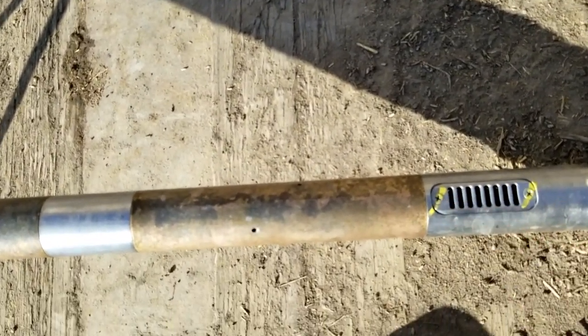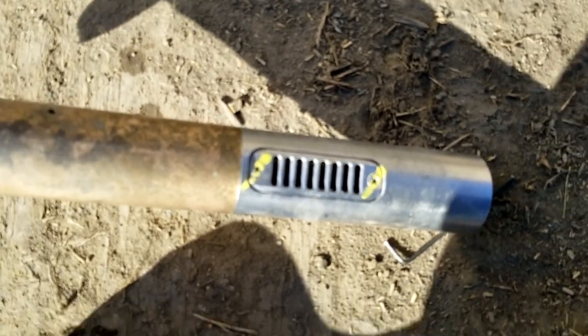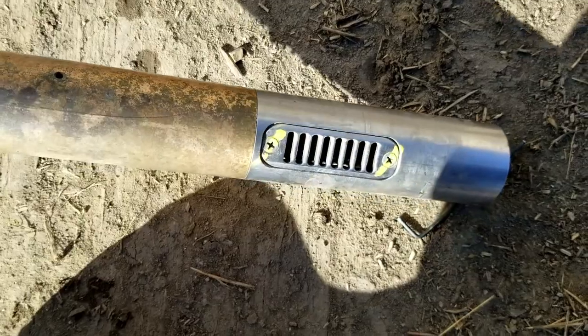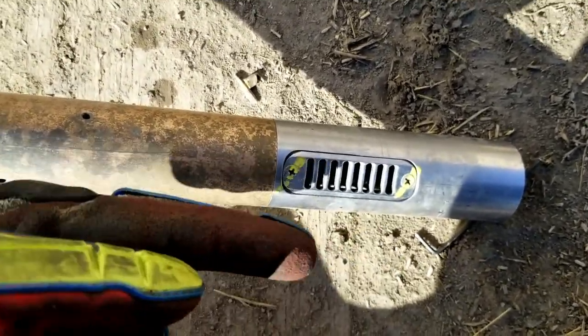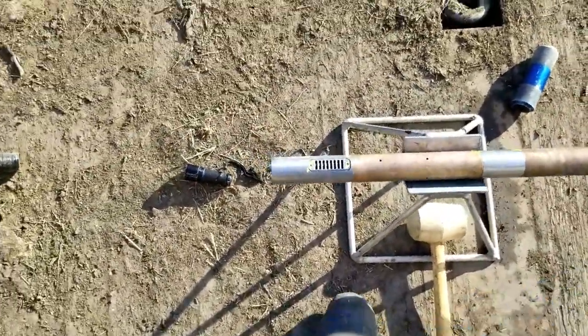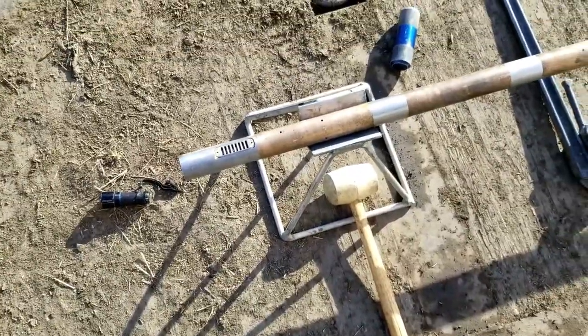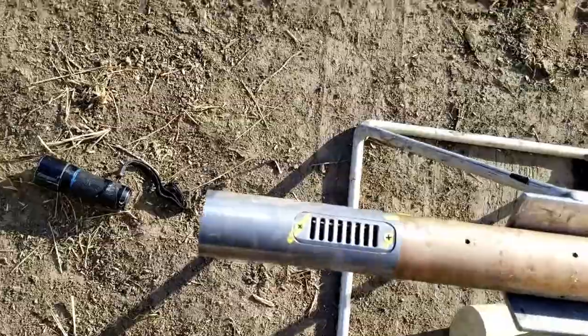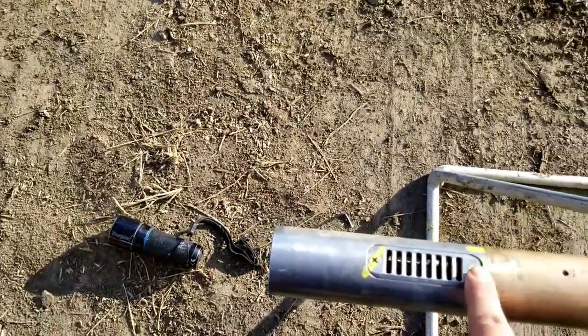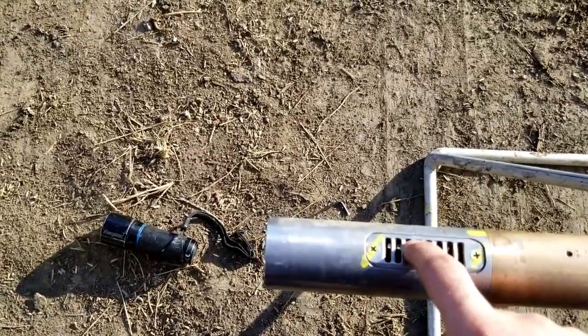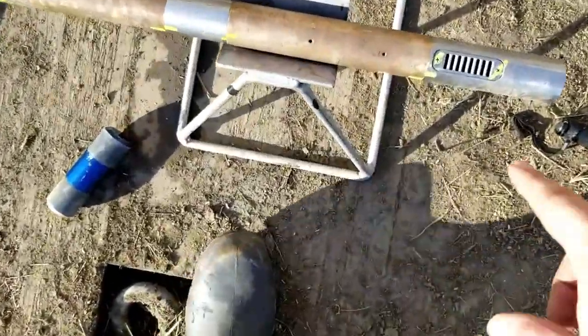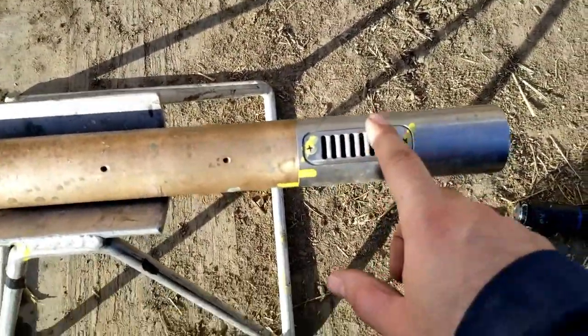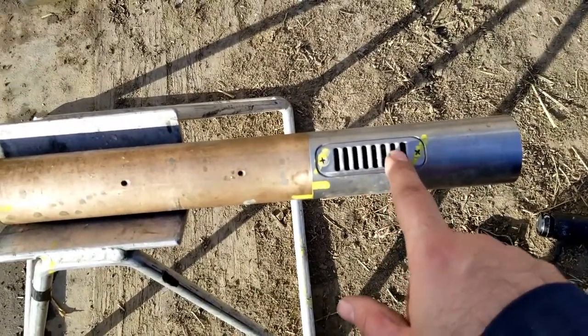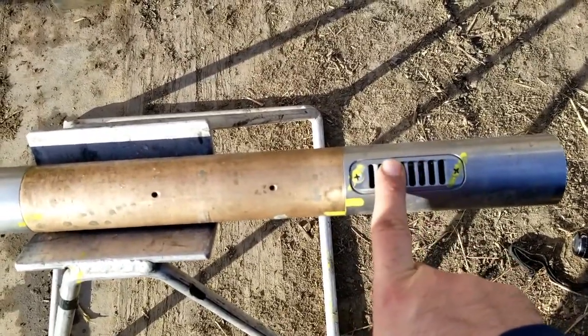So this little thing that we'll talk about later, right here, there's a screen, and behind that screen there's a poppet. I don't know if it's visible. That little poppet inside will reciprocate in and out. For the tap test, as explained earlier, I had to check that my pulsar poppet is moving. I take out these two screws, take out this screen, and put my finger on the poppet inside. With a little pressure of my finger, the poppet should be strong enough to move my finger back and forth.